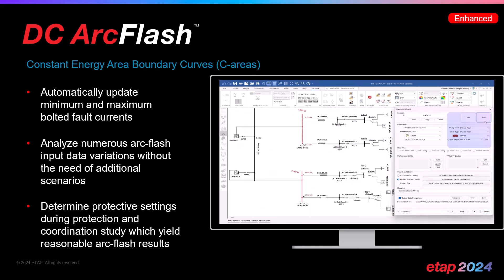And using that area, you can get a certainty region, which can help you determine the correct protective device settings and make your protection and coordination study more reliable when you have a situation where the data itself is not as accurate. So, without knowing the accuracy of the data, you expand the possibilities, and then you use the possibilities to set your protective device settings, which can give you more reasonable arc flash results more quickly and get you into compliance in a faster fashion.